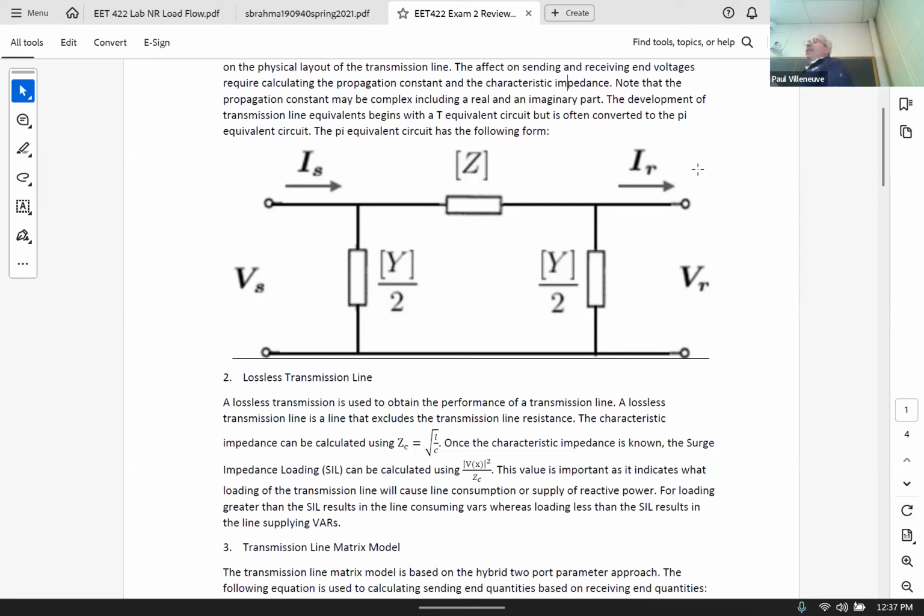And both of those can be negative. Overly drawing reactive power means your voltages tend to go really low, and you have to do a lot in your system to increase voltages to that plus or minus 5% nominal. But the other end is bad too. If you're underexcited or under the SIL, I should say it's a better expression, the concern there is that your voltages float too high. And which one is worse? They're about the same, right?